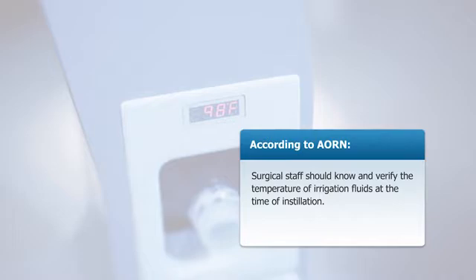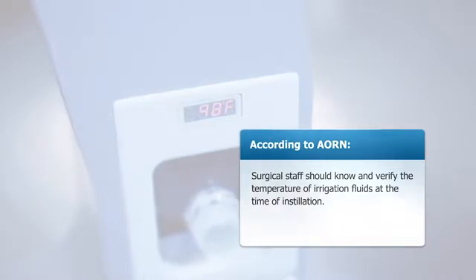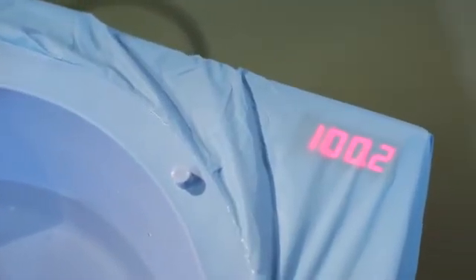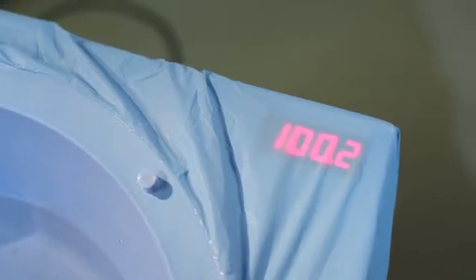According to AORN, surgical staff should know the temperature of irrigation fluids at the time of instillation. The Intratemp System features a visible display that allows constant fluid temperature control and monitoring during the surgery.